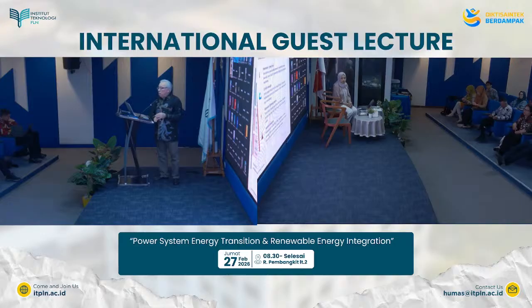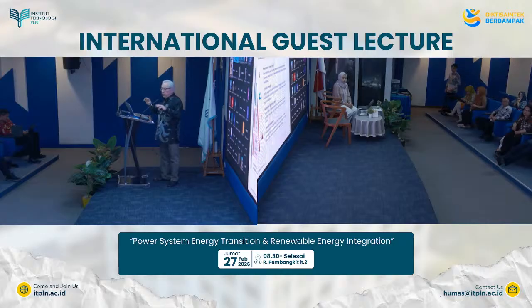So you can design n-1, and for some really, really critical systems, you can do n-2, which means you lose two major components of your system and still be able to operate normally, right? No loss of power, no loss of operating standards. Now, resilience means, and people also design for this, if there is an extreme event, storm, flood, more than a few losses of generation, how fast can you recover? Can you absorb the shock without a blackout? So, as different from reliability, reliability means everything works as normal if you lose something. Resilience means if you have a major loss of major components, you can recover quickly.